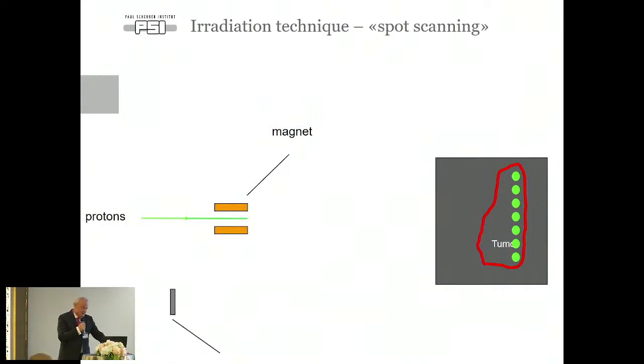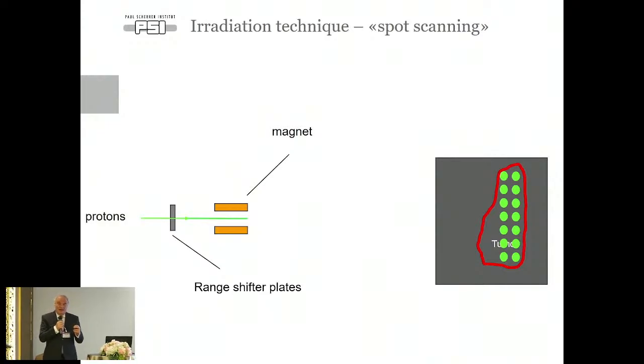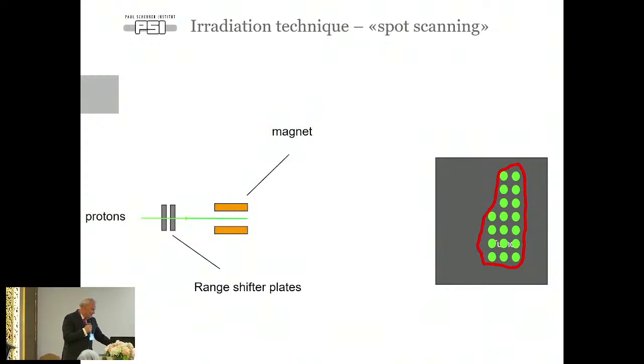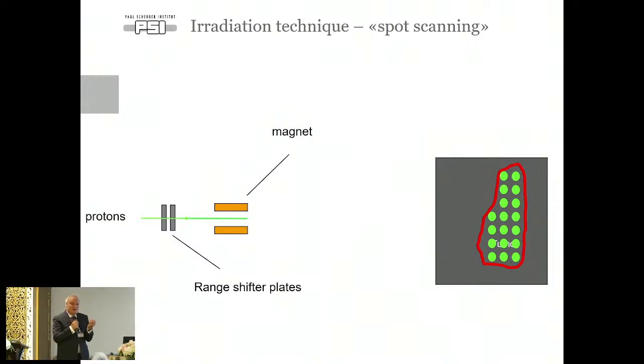We bring material into the beamline and then repeat the scanning. And this material means that the protons lose a little bit of energy, which means they don't reach that far in the patient. And we get a second line, but a bit more proximal. And now it's clear how this continues. You can change the energy again, adapt the range of the scanning field. So with this technique, it's possible to cover 3-dimensional volumes inside the patient without the need for patient-specific hardware. You don't need collimators here.